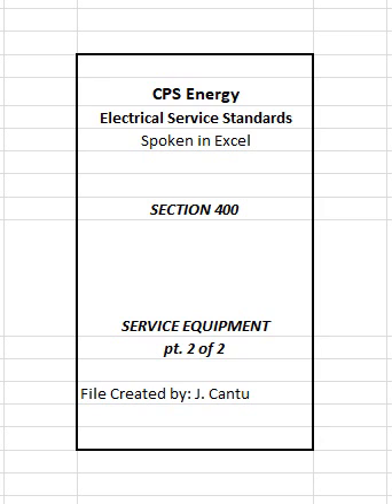407.1 Additional service disconnecting means, fire pump. The one or more additional service disconnecting means permitted by the NEC and Section 200 for fire pumps, and with special permission, for emergency systems, legally required standby, or optional standby systems shall be installed remote from the 1 to 6 service disconnecting means for normal service to minimize the possibility of simultaneous interruption of supply. Note: metering equipment for fire pump shall be grouped adjacent to other metering equipment associated with the building service and permanently labeled as fire pump metering equipment.